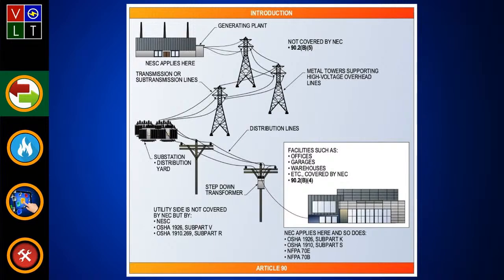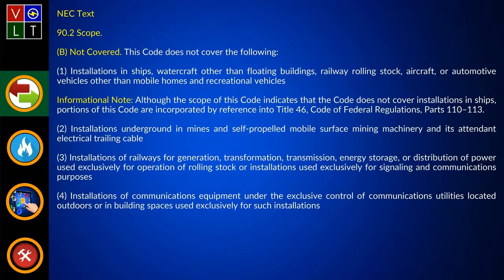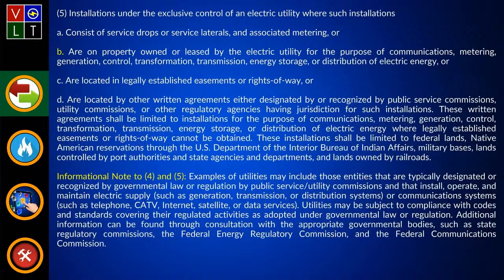When you look at the National Electrical Code and pick up 90.2B and look at the requirements there, you get down to B5 and it talks about installations under the exclusive control of the electrical utility. It gives you A, B, C, D, but basically it's telling you these are items that are not covered.